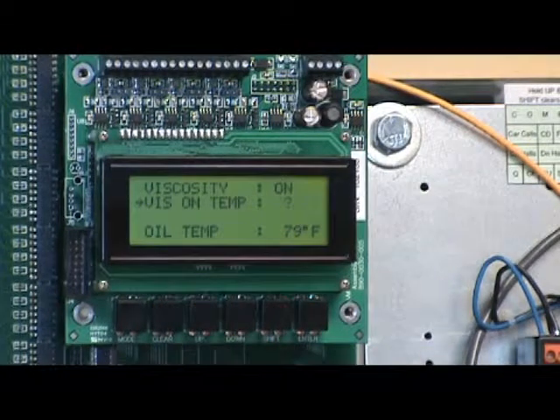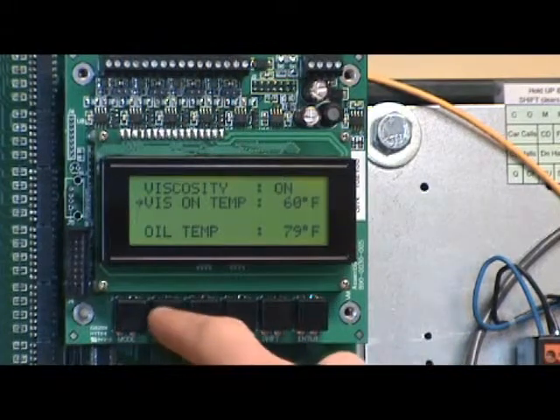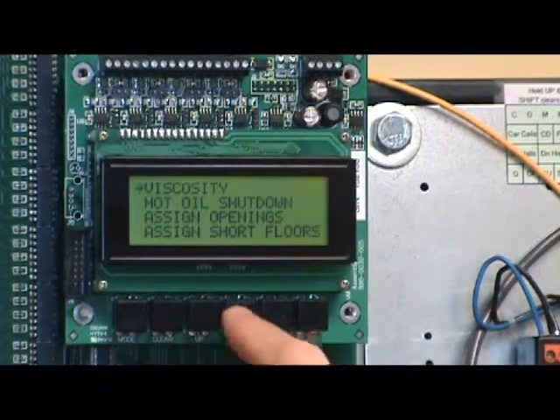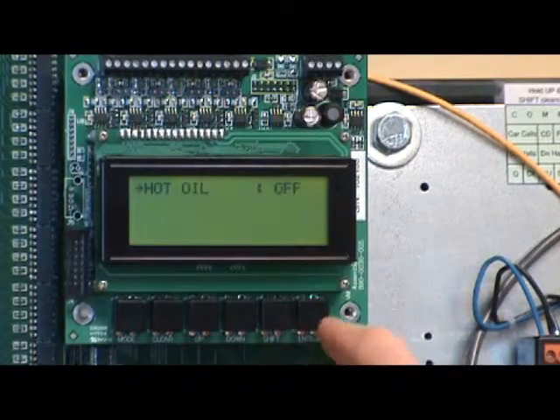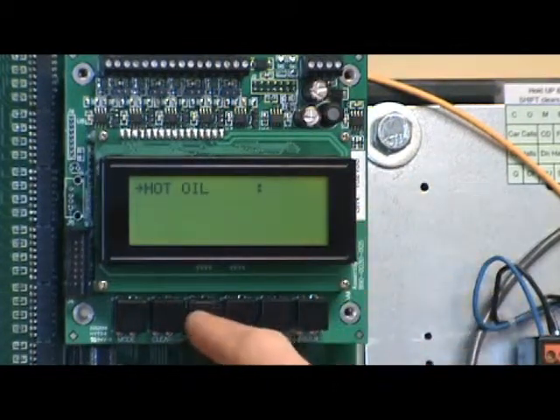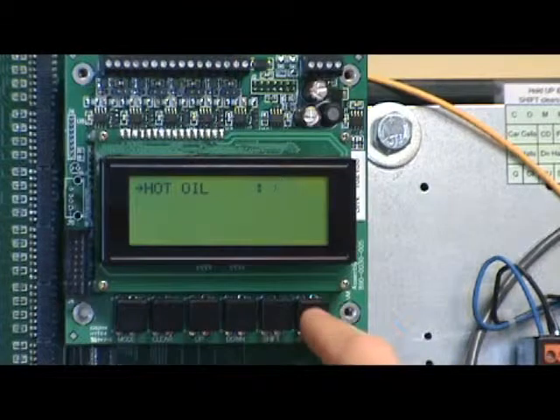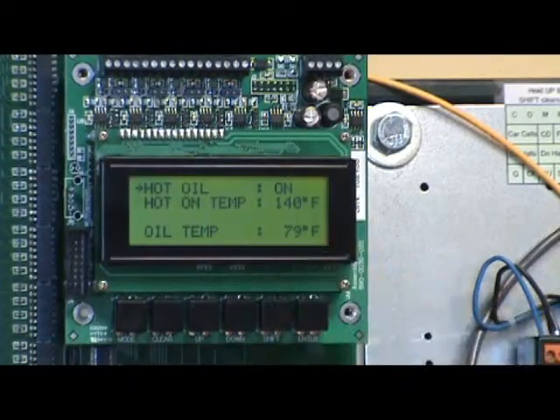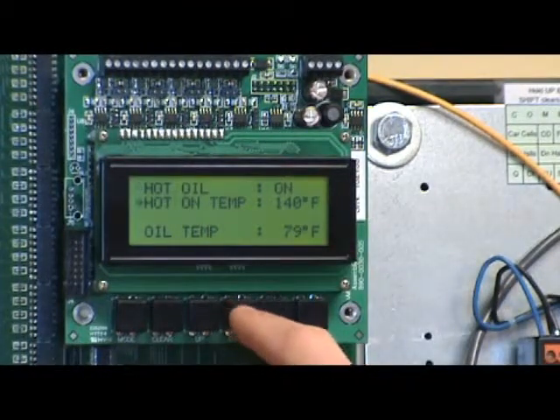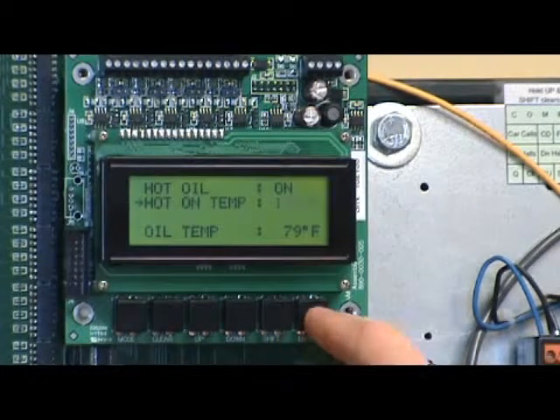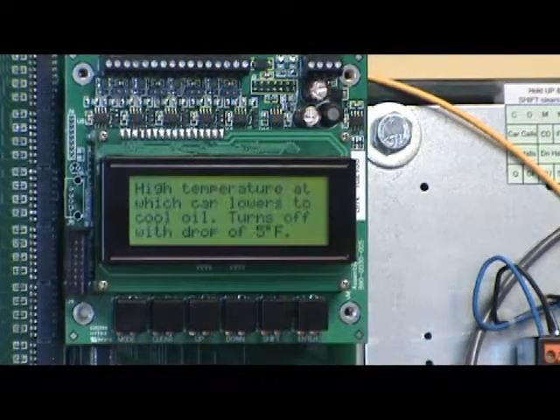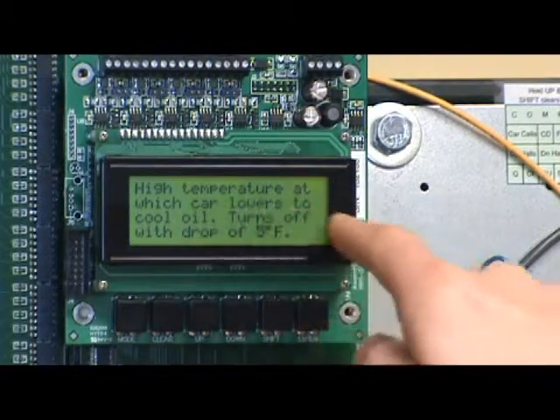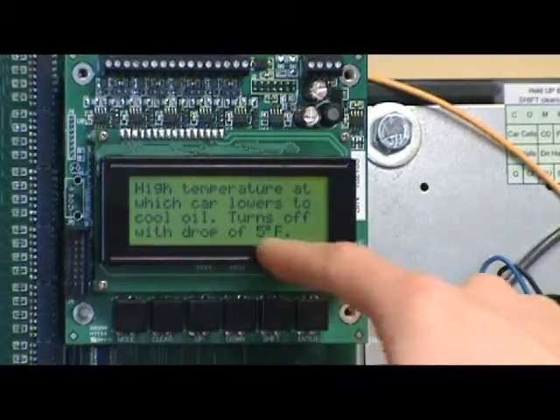If for some reason you get a call on the system while it's in the viscosity operation, the elevator will just take off and head for that call. I'm going to hit shift again. I'm going to go clear and go back to one more, and we're going to turn on the hot oil. Hot oil is off. I'm going to hit enter again. Use the up arrow until it's on. Hit enter, and now this one's set for 140 degrees. I'm going to hit the shift button to get the explanation of what that is. And it's going to say high temperature at which car lowers to cool oil. Turns off with a drop of 5 degrees.